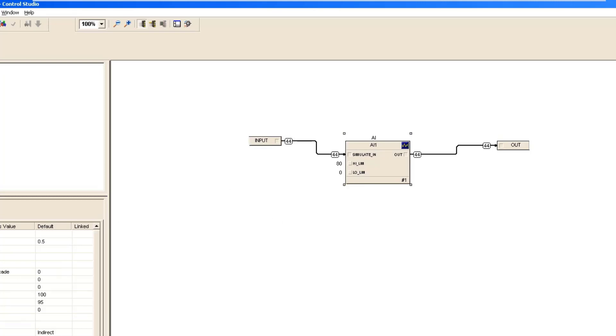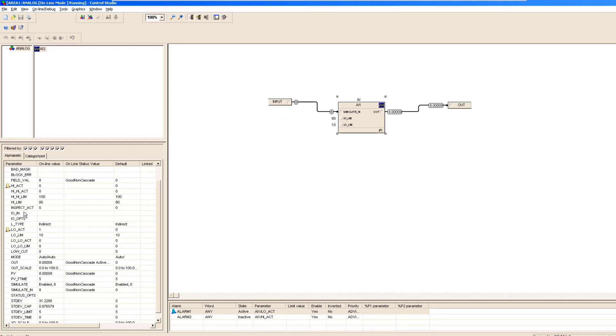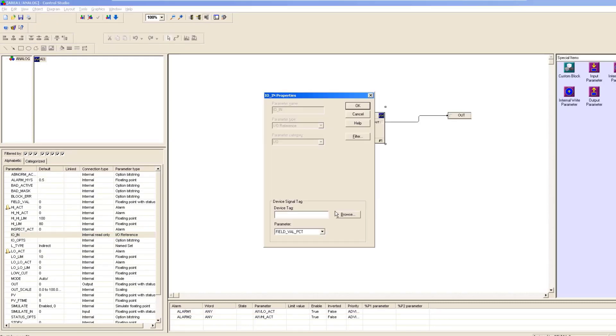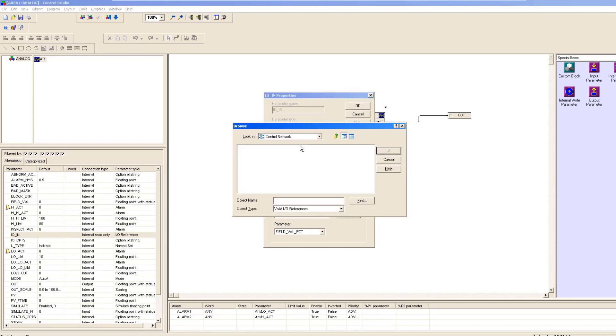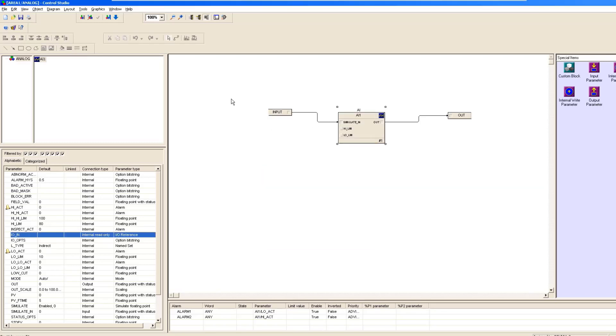So if you give a PV_FTIME value, the change will not be immediate — rather it applies some delay. This is the simulated environment. If you want to get your signal from the field, double-click on IO and Browse. Whatever input devices and instruments are connected to your input modules, all channels will appear here and you can select your channel and the signal coming from the field. Since we are in simulation, we won't select that and will continue using the simulation environment.